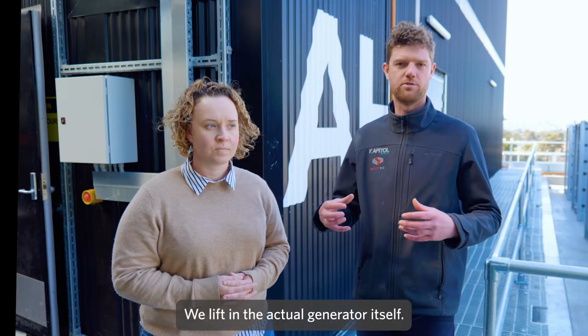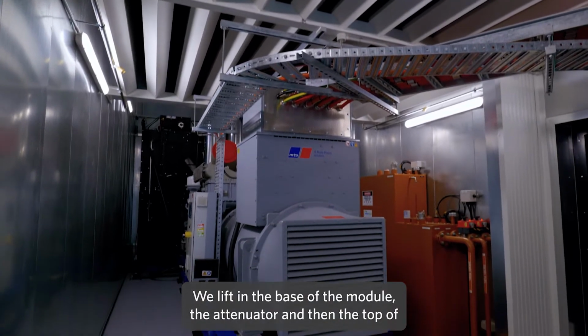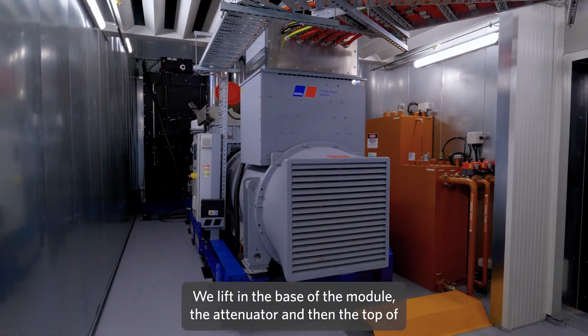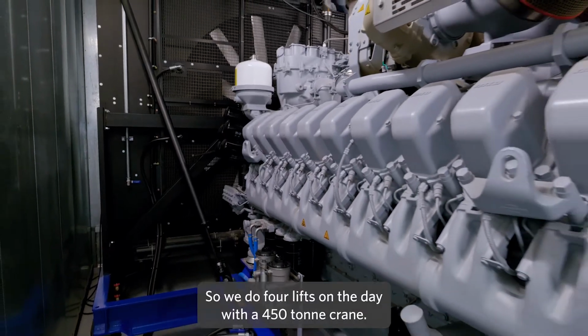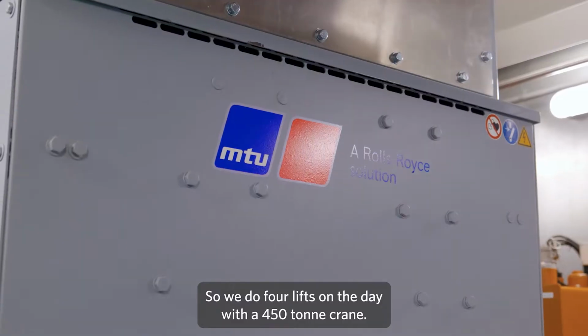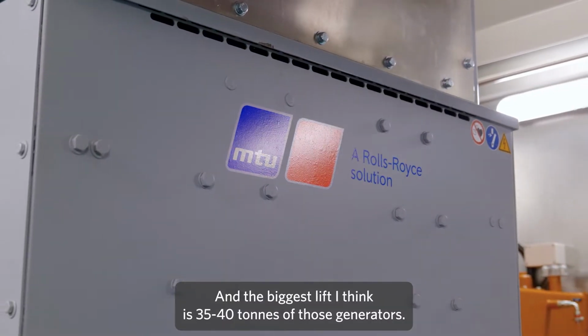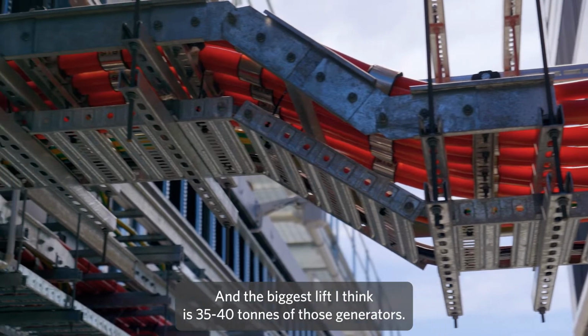We lift in the actual generator itself, the base of the module, the attenuator, and then the top of the acoustic enclosure. We do 4 lifts on the day for these with a 450 tonne crane, and the biggest lift is 35 or 40 tonnes for those generators.